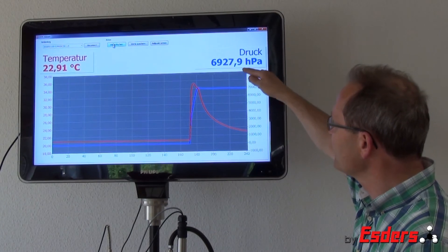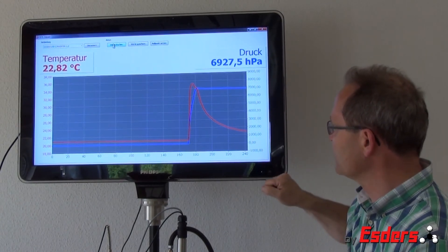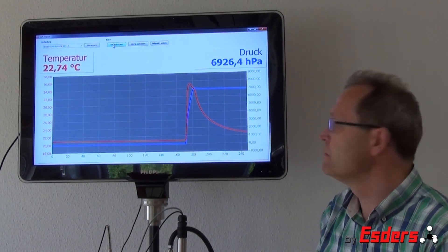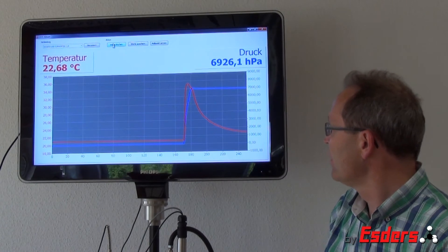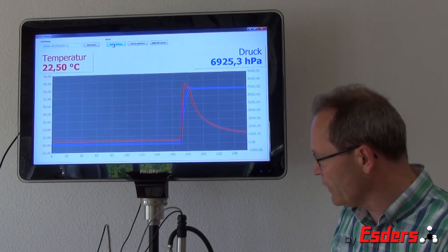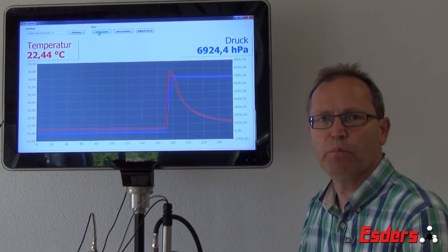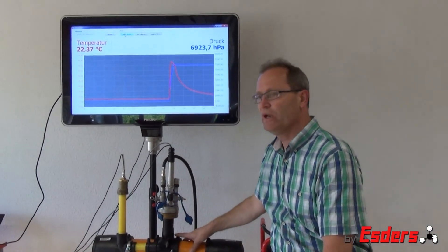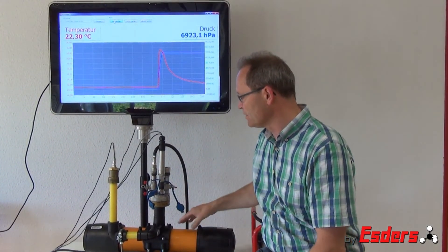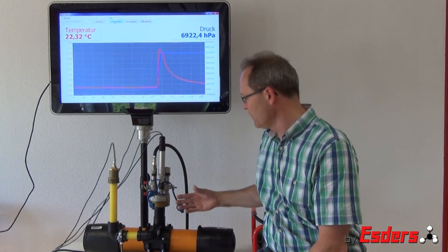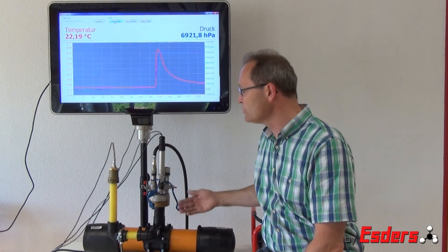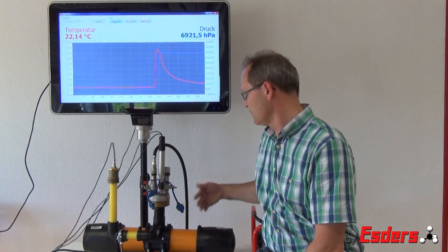It's not very much but we can see a decrease of the pressure. This decrease depends on two influences: one is the falling temperature, and the second is that we use a plastic pipe, a polyethylene pipe. Polyethylene will expand if you put pressure on it. This expansion will stop after a certain time, but this time is not reached within some minutes — it usually takes more than an hour.